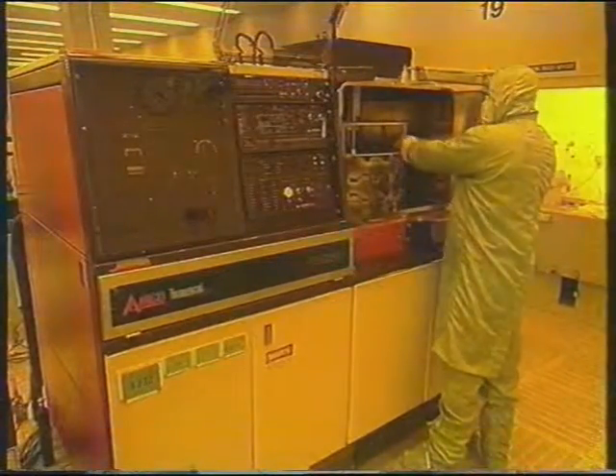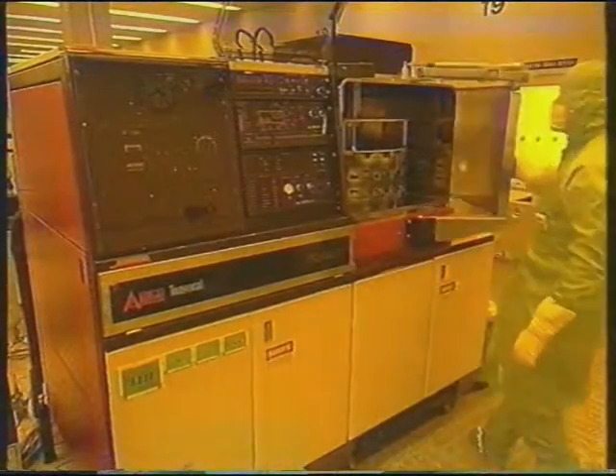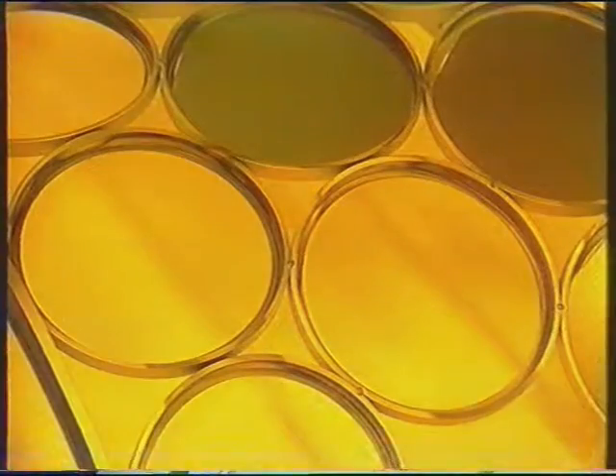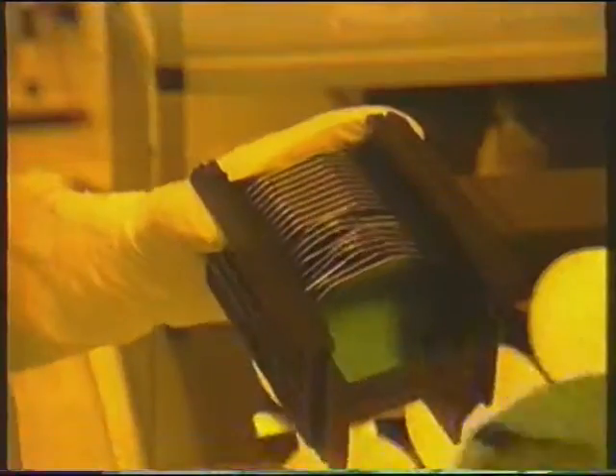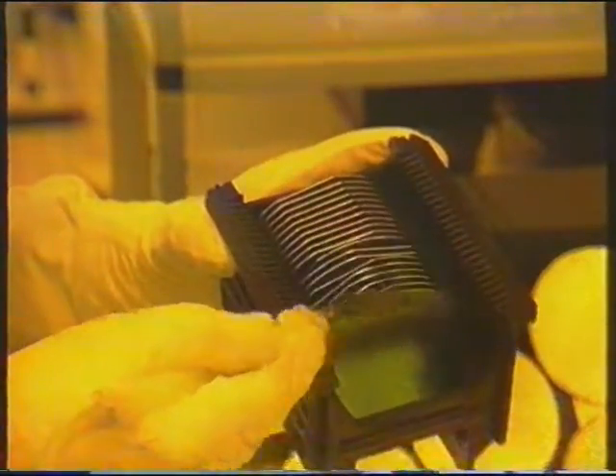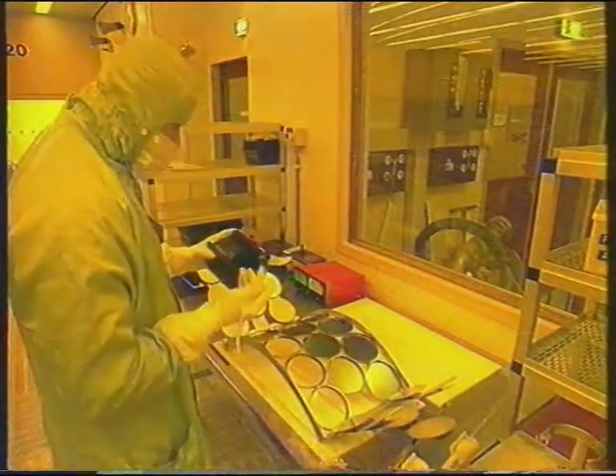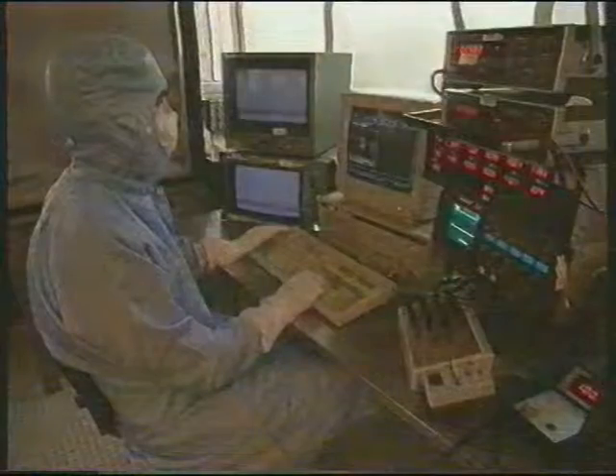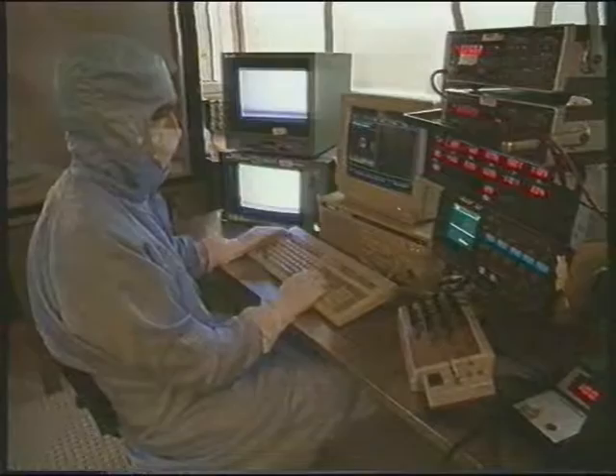The individual elements of the sensor must be connected together as required by the sensor circuit design. This is done by a metallization process, bonding these elements together. Once the metallization process is completed, it is carefully checked to ensure that all correct connections are made and that no short circuits or faults are present. When these checks are completed and we are sure that the sensor is perfect at this stage, then the final assembly stage can be started.